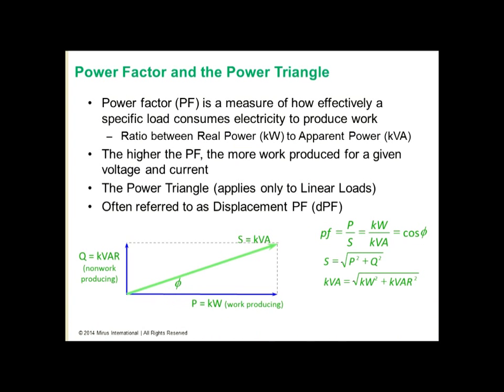For those trained in electrical theory, the concept of power factor used to be fairly simple to understand. Power factor is a measure of how effectively a specific load consumes electricity to produce work. It is the ratio of real power in kilowatts to apparent power in kVA. The higher the power factor, the more work produced for a given voltage and current. The power factor triangle, shown on this slide, applies only to linear loads, however, and it is often referred to as displacement power factor, or DPF.